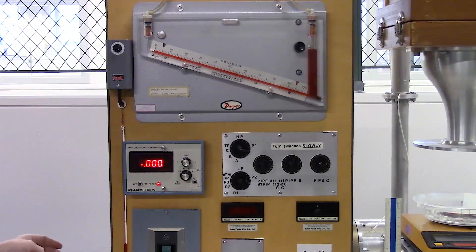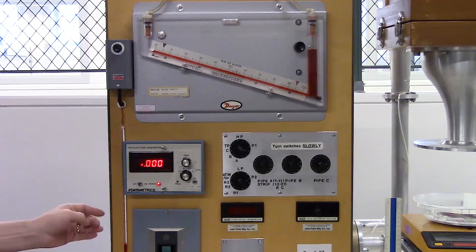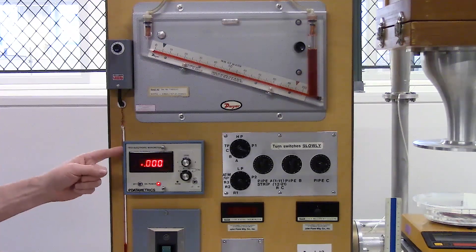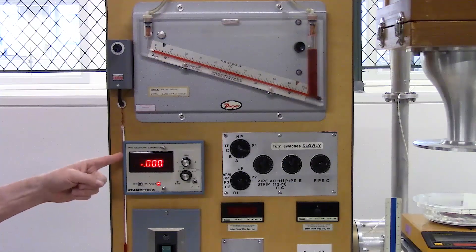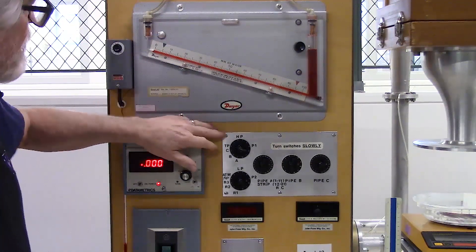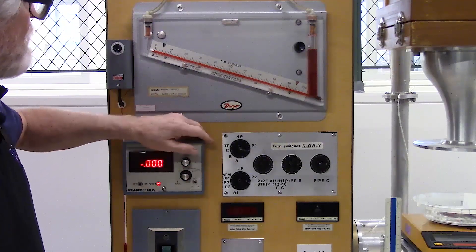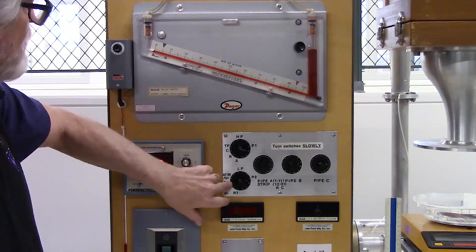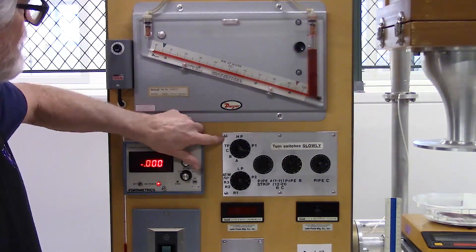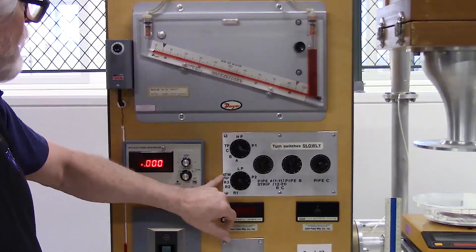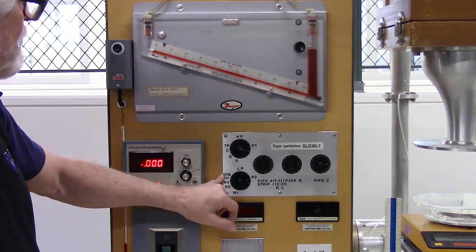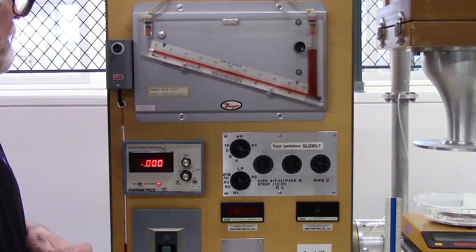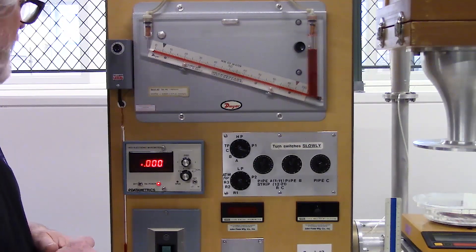The pitot tube is routed through a differential pressure transducer. The signal of that transducer is sent to this digital manometer here. That reads out in millimeters of mercury. We can connect various signals to that differential pressure transducer. We have a high pressure side and a low pressure side. In our case the high pressure side is connected to the pitot tube. The low pressure side is connected to atmospheric pressure. We can use these switches here to connect various pressure taps through that transducer and we'll go over that more in a future lab.